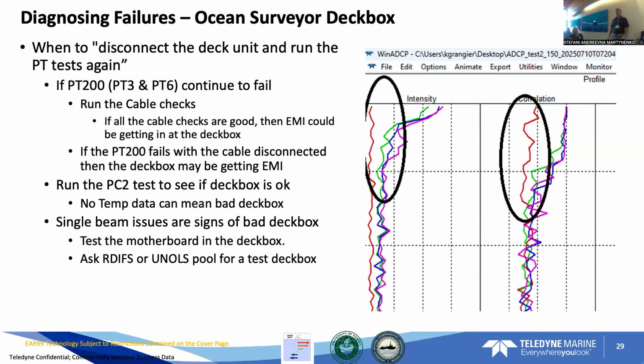There's a bunch of tests we can do on the deck box, but if you want a quicker test check, we can send you a deck box, then you can install it and test and see if it's working or not. We have some, and the SIO UNOLS pool has some that they can share. Another test you can do is run the PC2 test, and if you don't see any temperature data coming out, that's another sign that the deck box has failed. If we're looking at just the raw intensity and correlation data showing on one beam, that's a sign that the deck box has failed. So we want to run all these tests again.